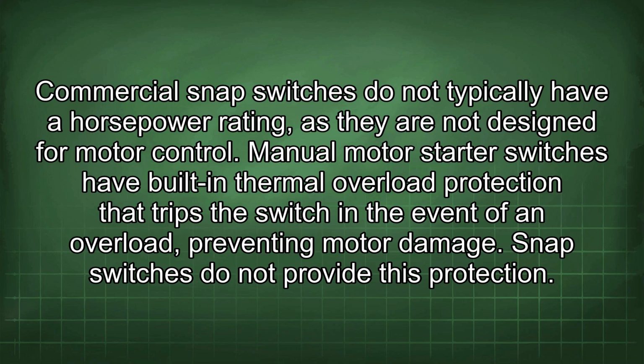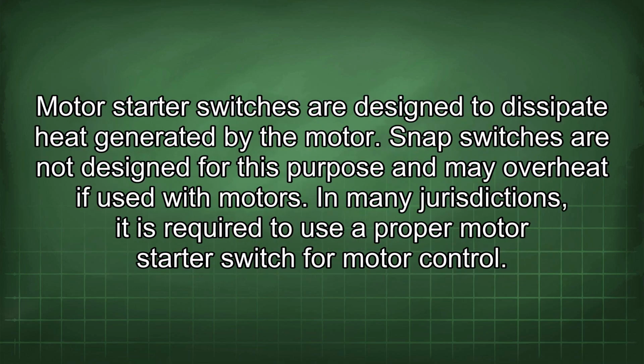Manual motor starter switches have built-in thermal overload protection that trips the switch in the event of an overload, preventing motor damage. Snap switches do not provide this protection. Motor starter switches are designed to dissipate heat generated by the motor. Snap switches are not designed for this purpose and may overheat if used with motors. In many jurisdictions, it is required to use a proper motor starter switch for motor control.